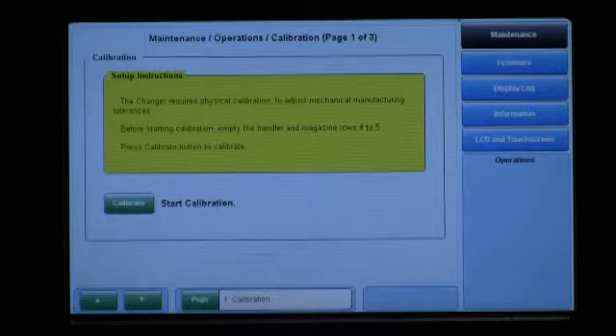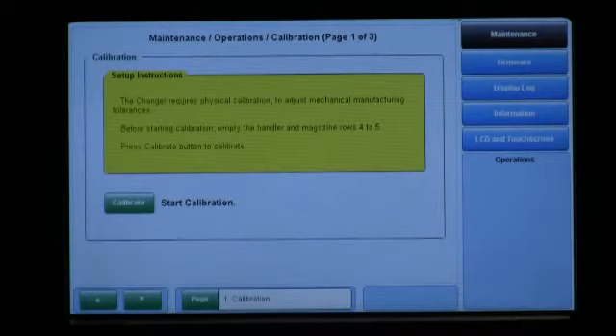Now please note, depending on the firmware revision of your library, you may not have this calibrate option in your library. If you do not have this option available to you, you will have to do one of two things. You can update the firmware revision of your library to the current revision, or you can enter a password into the library that will enable you to perform a calibration.